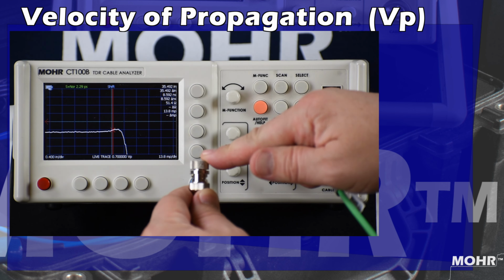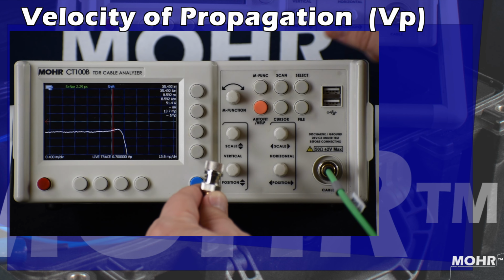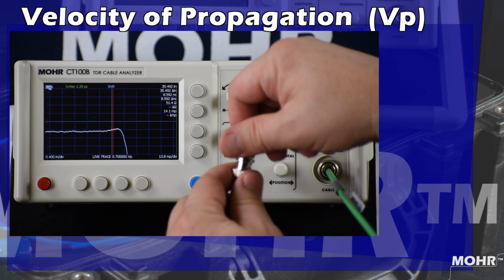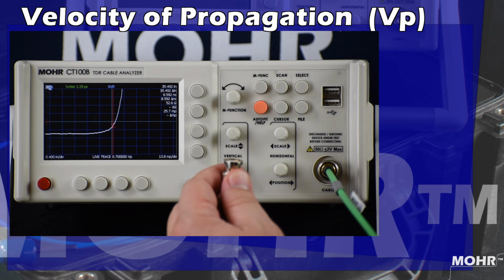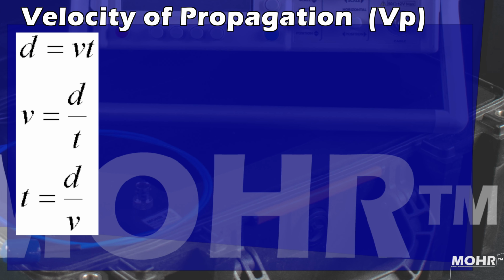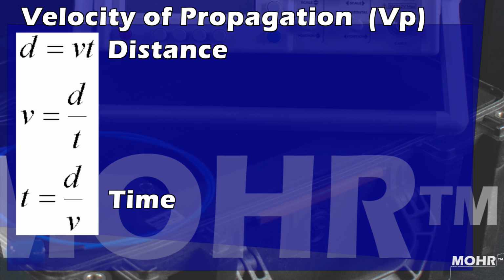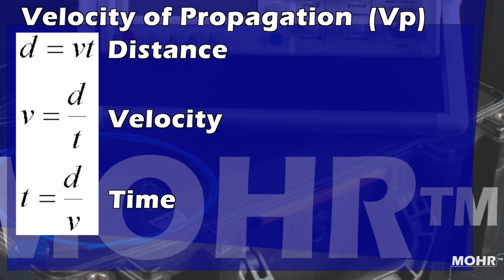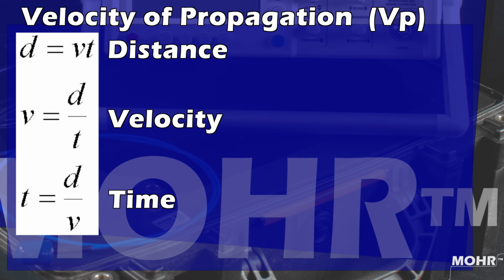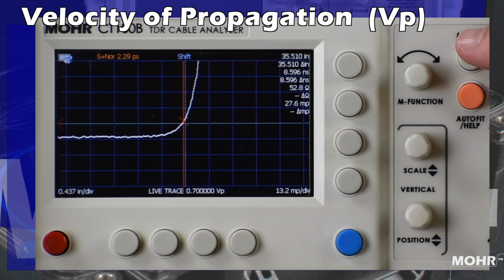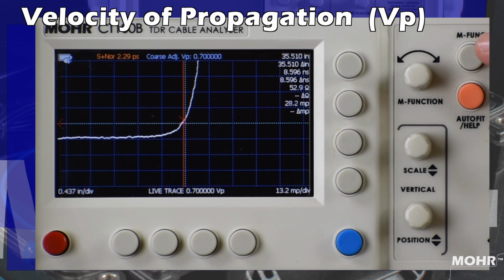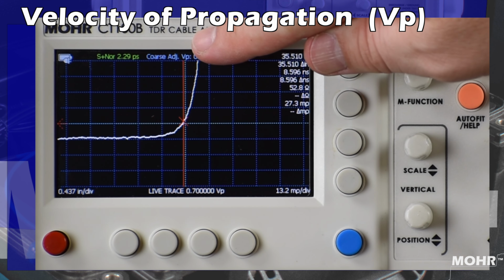It's important to note that a TDR measures in time, the time it takes to get to the measurement and back. That's how we come up with the equation of distance over time equals velocity of propagation, or VP equals D over T.